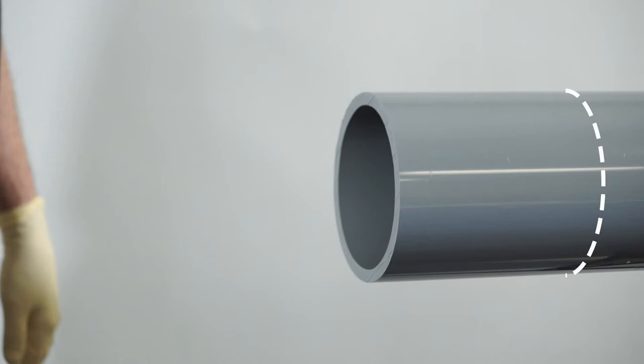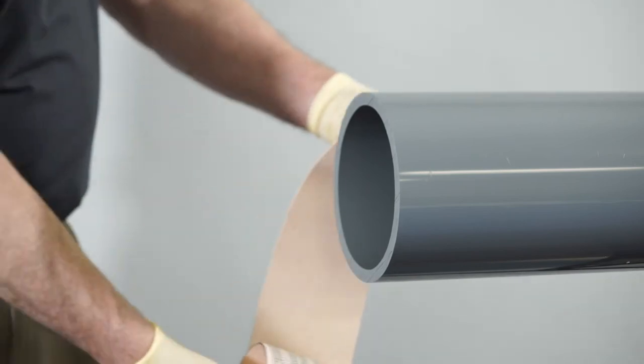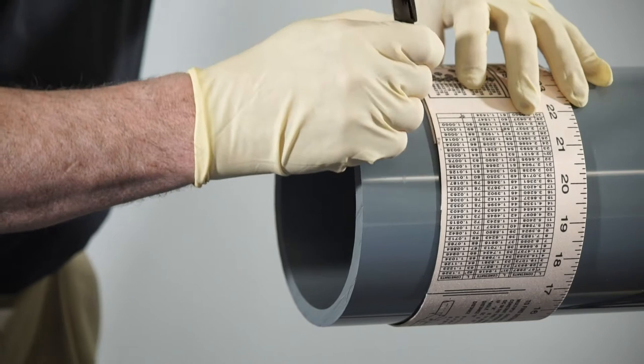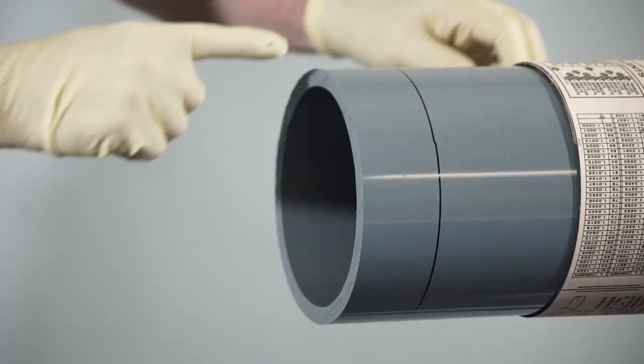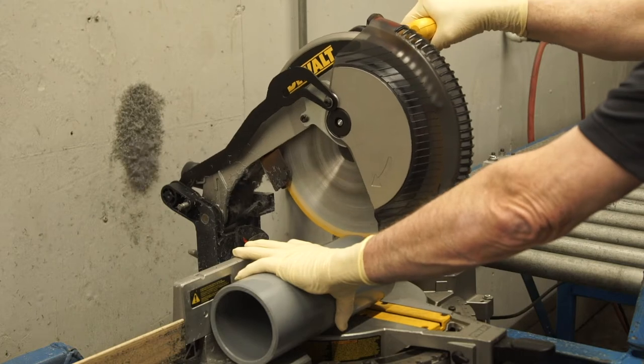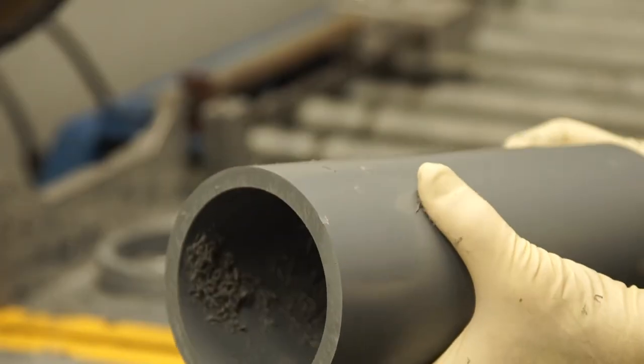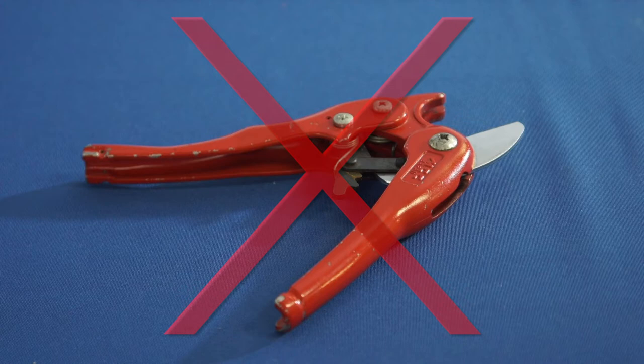The pipe must be cut as square as possible. A diagonal cut reduces the bonding area and thus the strength of the joint. An easy method to ensure a straight cut is to use any flexible straight edge to mark around the pipe diameter at the appropriate length for the cut. The pipe can be cut with a wheel-type plastic tubing cutter, power saw, chop saw, or fine-toothed saw. George Fischer does not recommend the use of ratchet cutters as they may split the pipe during cutting.